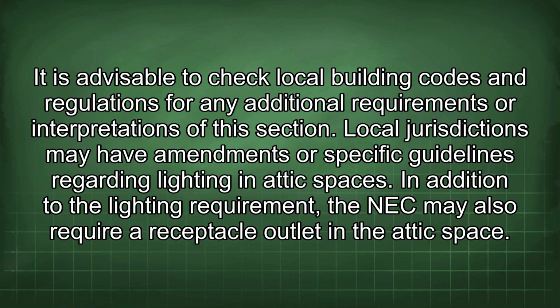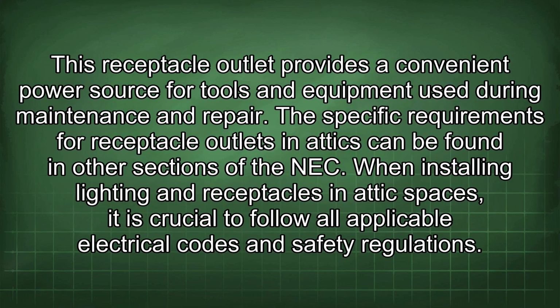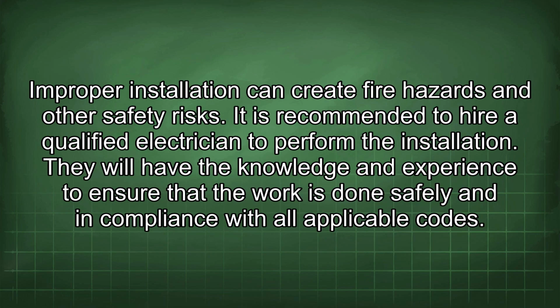In addition to the lighting requirement, the NEC may also require a receptacle outlet in the attic space. This receptacle outlet provides a convenient power source for tools and equipment used during maintenance and repair. The specific requirements for receptacle outlets in attics can be found in other sections of the NEC. When installing lighting and receptacles in attic spaces, it is crucial to follow all applicable electrical codes and safety regulations. Improper installation can create fire hazards and other safety risks. It is recommended to hire a qualified electrician to perform the installation.